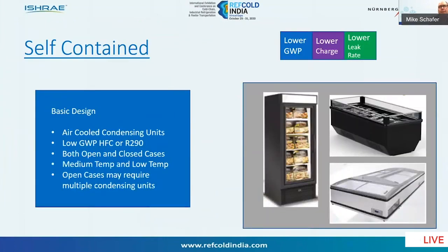And then the variation of microdistributed would be self-contained with R290, but there's a lot of effort around designing self-contained equipment to include either HFC or R290. In this case, I'll be more focused on the R290 systems. Once again, the strategies employed are pretty straightforward: lower GWP, lower charge, and lower leak rate. These types of cases would be both open and closed cases, low temp and medium temp. The open cases certainly utilizing R290 may require multiple condensing units. These would be air-cooled condensing units, by the way.